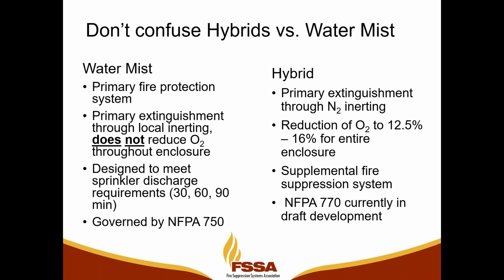Some of the key differences between hybrids and water mist, and we get these questions all the time: water mist can be used as a primary fire protection system. It could be used in place of fire sprinklers in various types of applications. From a water mist perspective, it doesn't reduce oxygen levels throughout the entire enclosure. It only does local inerting at the fire source, and it can be designed to meet sprinkler discharge requirements, whether it's 30 minutes, 60 minutes, or 90 minutes.